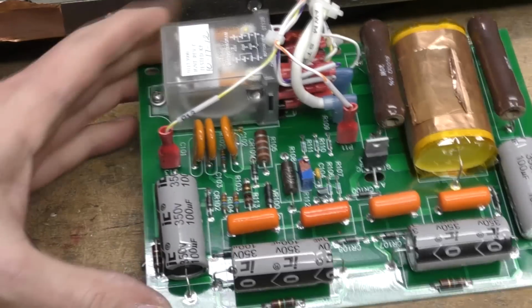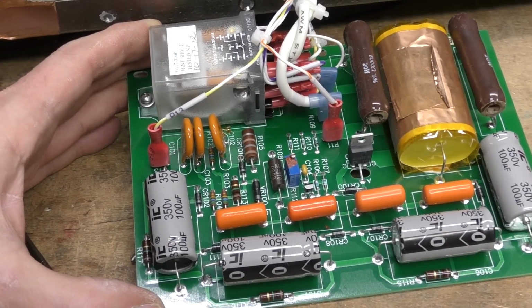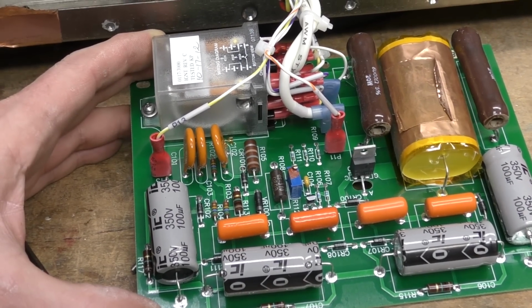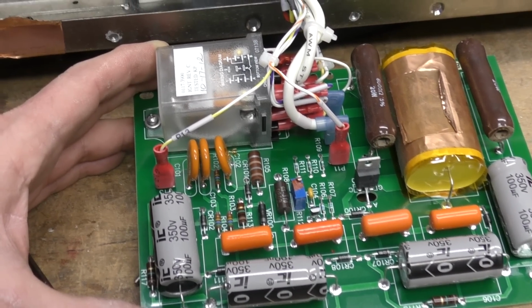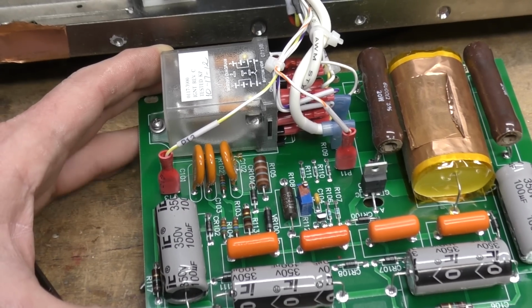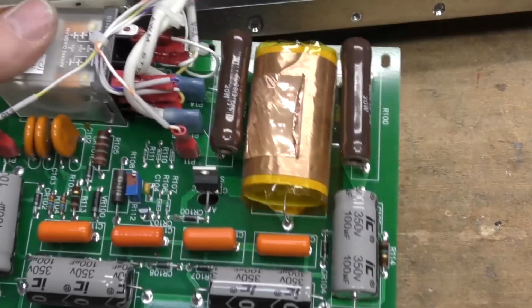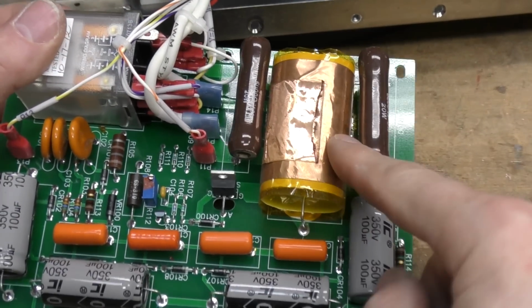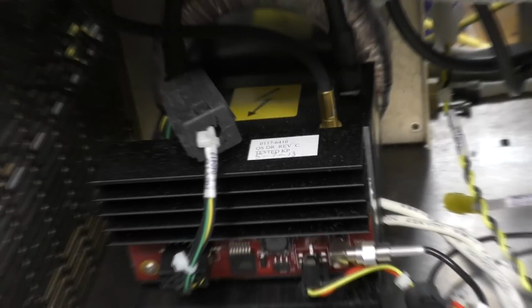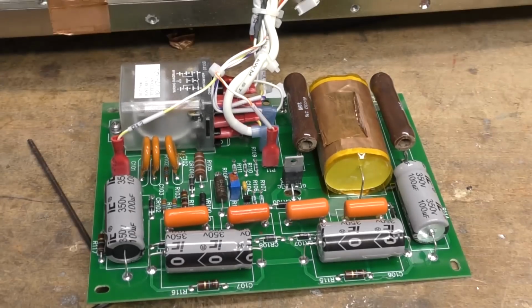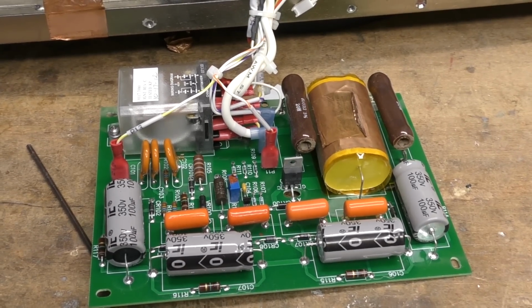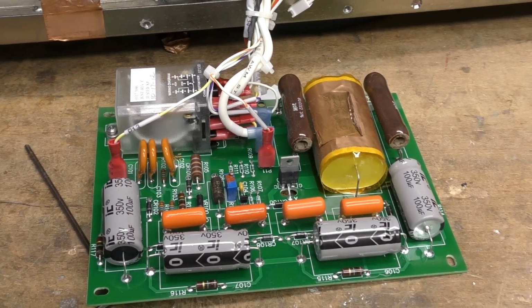I think this is the board that controls the ignition of the lamp. So these discharge lamps will have like a DC supply and then need a very high voltage supply just to strike it to start the plasma discharge. So it's probably going to be working by discharging this cap through this thyristor into a transformer, which we can just about see the high voltage symbol on the back here, and that'll be connected in series with the DC supply to the lamp. So it injects a high voltage spike on the supply to do the initial ionisation.